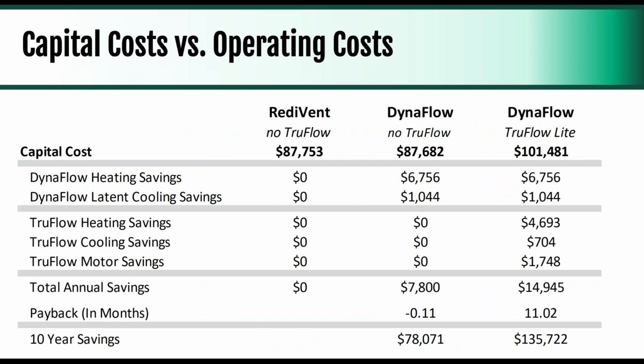And then lastly, capital costs versus operating costs. When we look at capital costs, again, we talked about these two being about the same, whereas with the demand control, it's more expensive. But when you look at annual savings over a 10-year period, the payback on having high efficiency hoods, because you're saving money on the mechanical side, is actually negative.